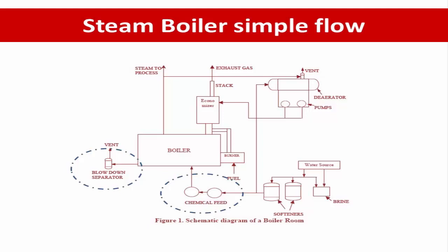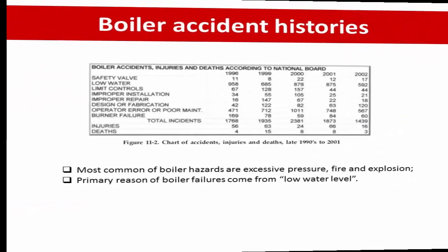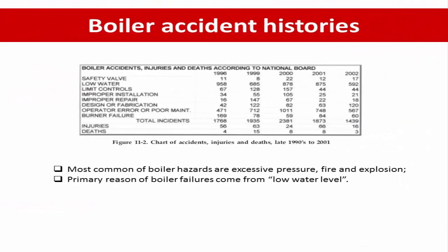The basic schematic diagram for the boiler is as shown in this picture. The major hazards of the steam boiler — the most common boiler hazards during the safety and hazard review are excessive pressure, fire, and explosion. The typical cause that can lead to boiler excessive pressure comes from low levels in the boiler, such as in the steam or water drum.